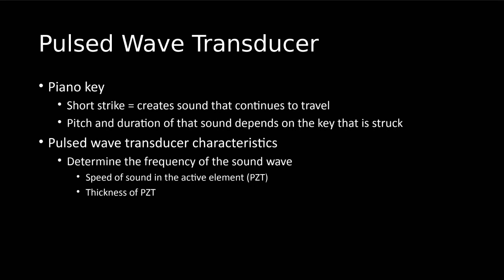So in the system, there are things that we can adjust, and depending on the transducer that we're looking at, the system could say, all right, here's my active element layer, but then I have all of these little wires that are connecting to different parts of it, and I only want to excite this part of the crystal or the active element, or I want to excite the entire part. So these are all things that we can adjust and we'll learn about, but that is all going to depend on what we are trying to do.